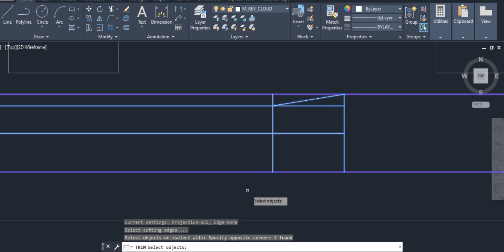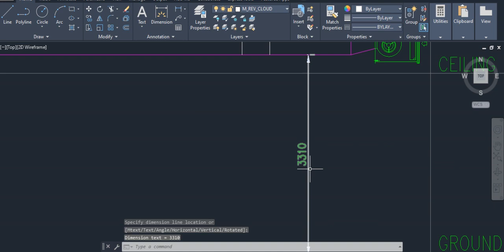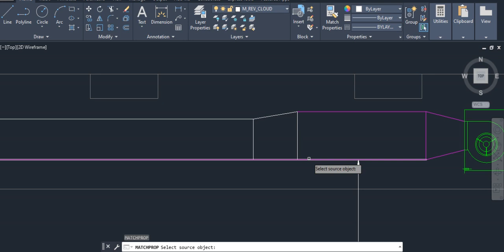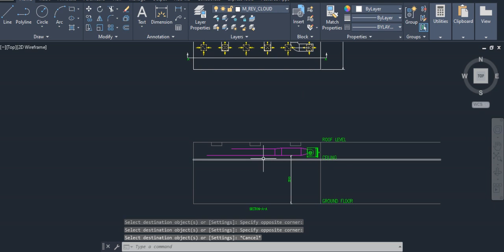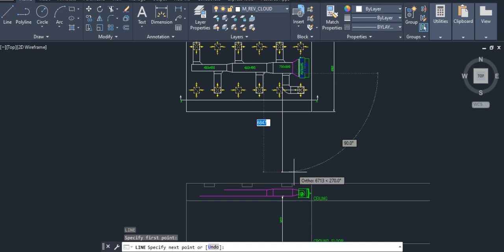Keep the bottom of duct flat everywhere, same for all ductings. So this bottom of the duct, 3310, should be flat. So we have to reduce from the top, not from the bottom. An eccentric type of reducer we can use here. If you are seeing from here, you can see this piece also.